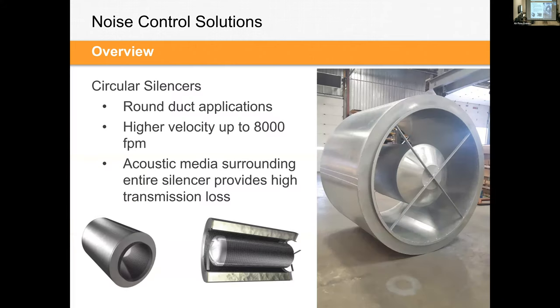Circular silencers are another type you may not be familiar with, and they're great for round duct applications. These have the acoustic media 360 degrees around the circumference. Again, they can be very large, this one is about 60 inches in diameter, or very small, 4 or 5 inches in diameter, depending on what you're trying to attenuate. They're also great for large airflow and large air volumes.